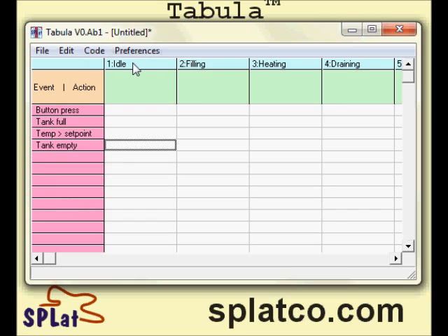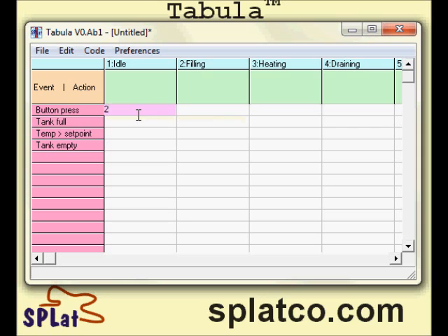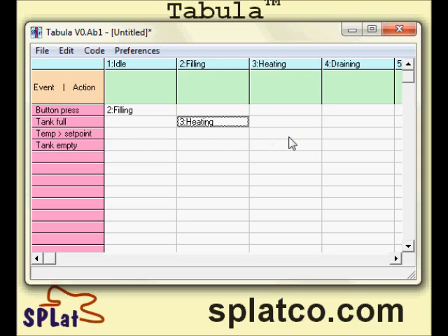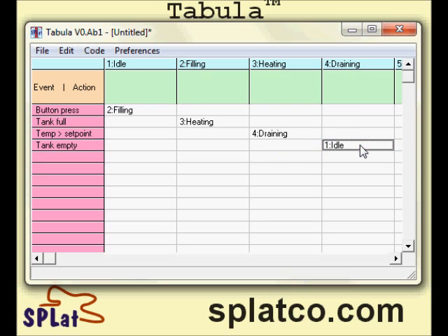So we have four possible events and four states. Now I'm going to define the transitions from one state to another. Imagine the machine sitting in the idle state — we're expecting the operator to press the button. When the button is pressed, we go to the filling state: I simply type the number 2 in that cell, which is state number 2, the filling state. When we're in filling, the tank is going to be full, so in that cell intersecting filling and tank full, we put a transition to state 3, heating. When heating and temperature exceeds the set point, we go to state 4. And in state 4 draining, when the tank is empty, we go to state 1 and complete the cycle.